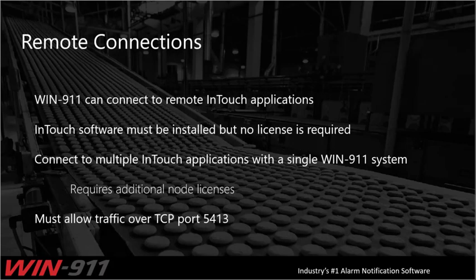For remote connections, WIN911 can connect to remote InTouch applications. If you'd like to run it on a separate server from InTouch, you just need to install InTouch on the same system where WIN911 is. It does not have to be running or activated with a license — it just places those Wonderware components on the system that we need to connect to your remote Window Viewer applications. We can also connect to multiple InTouch applications from a single WIN911 system, though that does require another node license from the WIN911 side.